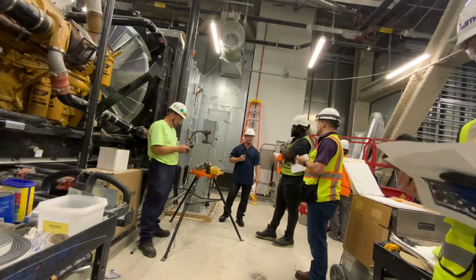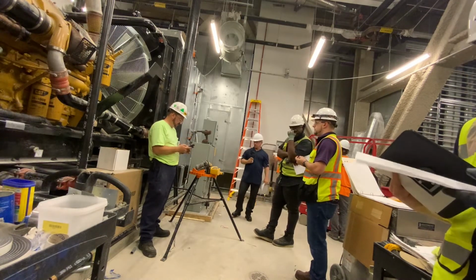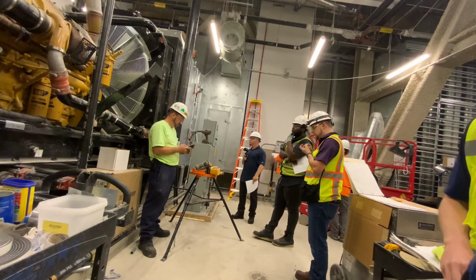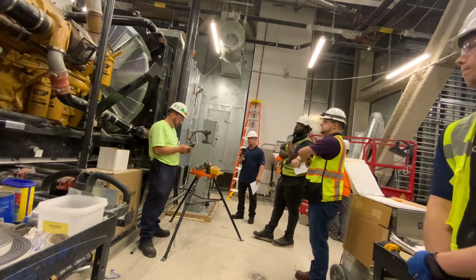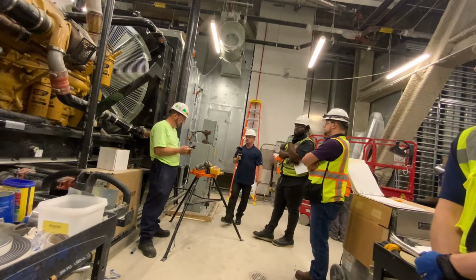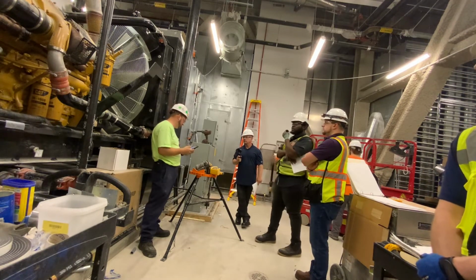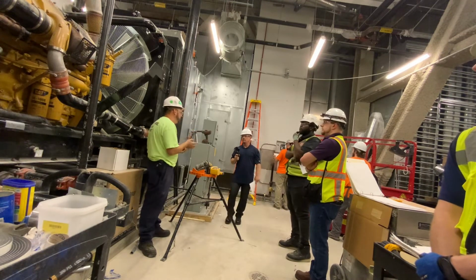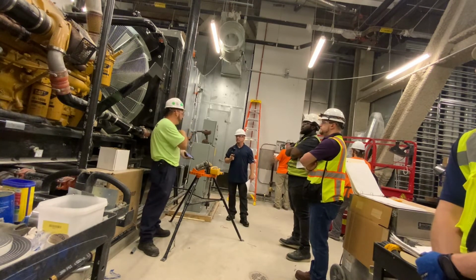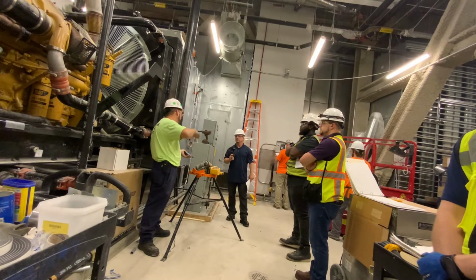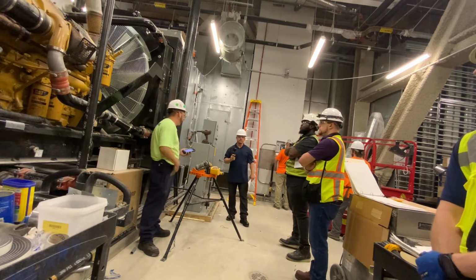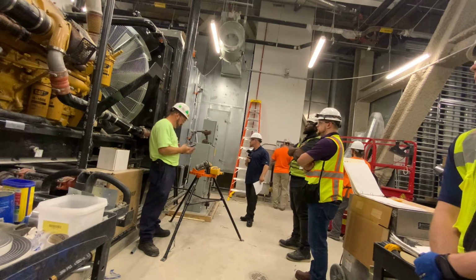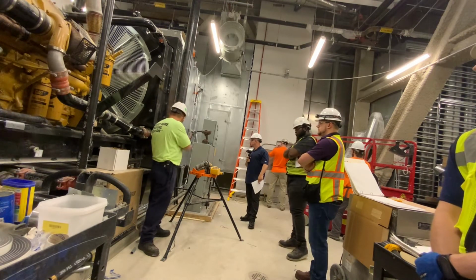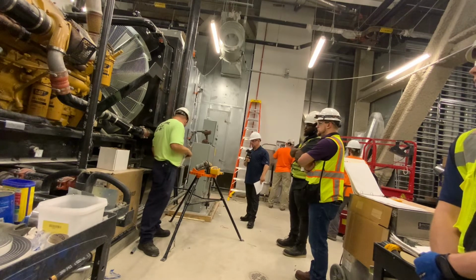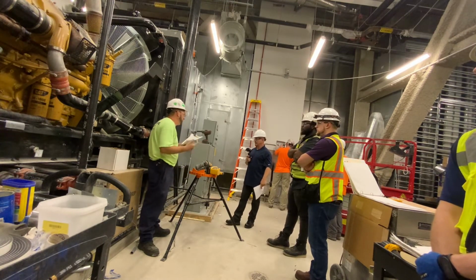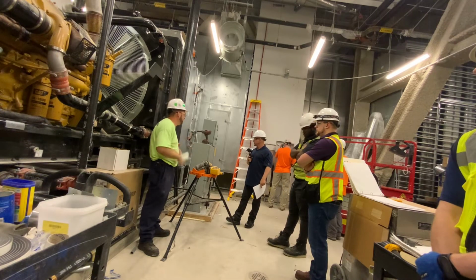What's the burn, half tank? Yes, correct. So it's going to be roughly, let's see, about 70 gallons an hour at full load. Half load is pretty much a linear scale, like half load's 36 gallons, so it's only in the beginning where you lose a bit, because you've got the mass spinning with no output, so you lose a little at the start, and then the scale goes up on a linear curve. Just to give you a rough idea, you could probably go - well, I wouldn't run the tank that low if you were running, but you could consider 15 to 20 hours.